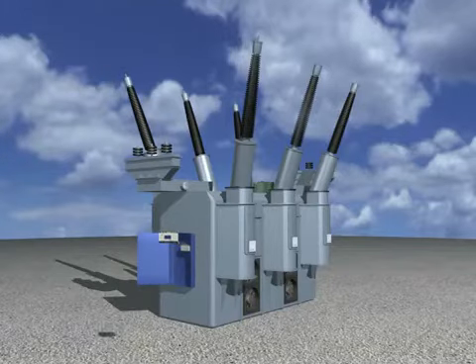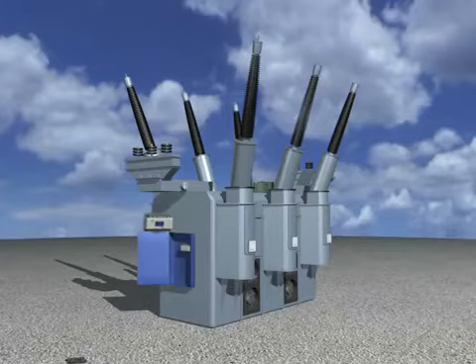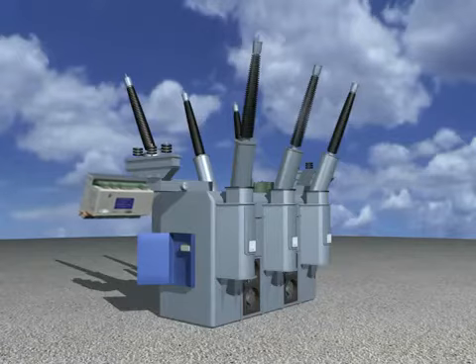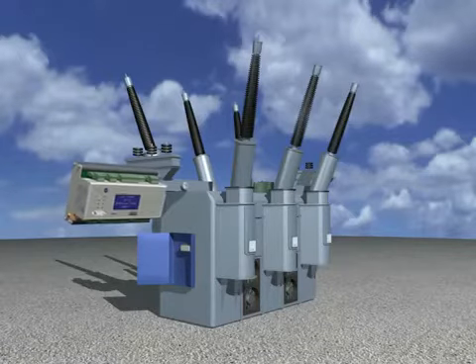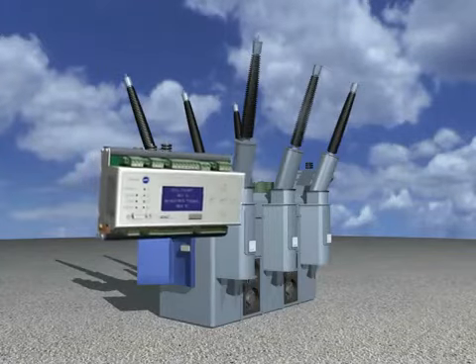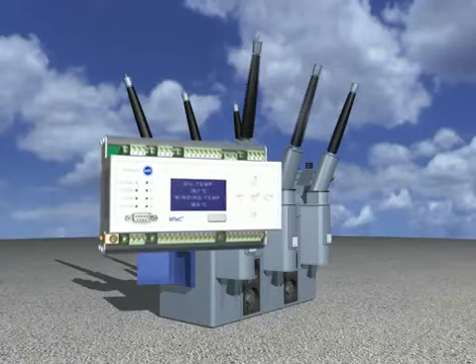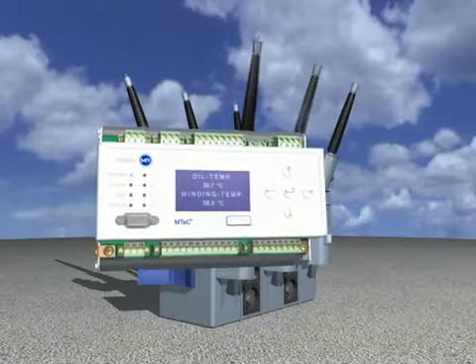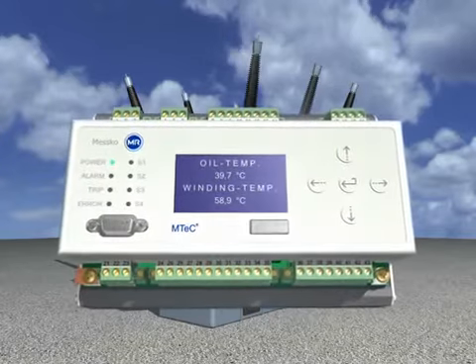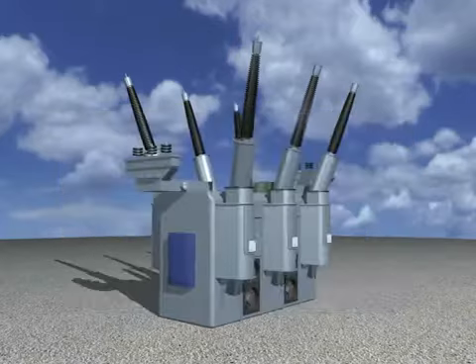This ability can be increased by using temperature monitoring devices with communication capabilities and converting the device from a single monitoring relay to a temperature management tool. The ideal winding temperature indicator will precisely reflect the behavior of the windings of a transformer, immediately indicate the highest temperature under all load conditions, and initiate appropriate cooling measures. The MTeC EPT202 generation of devices meets these requirements, and then some.